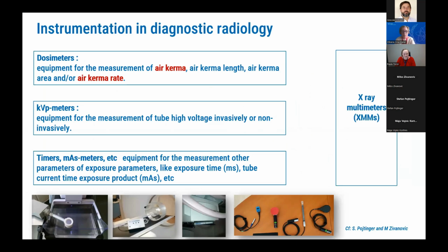For the measurable quantities in diagnostic radiology, we use different instruments that were extensively covered in the previous two talks. Both Miloš and Stefan mentioned different instruments aimed at those measurements, mainly in terms of air kerma, also for tube voltage assessment and measurement of other parameters like exposure time or tube current exposure time product, total filtration, half-value layer, and so forth. But in the last 20 years, all these parameters and quantities are somehow combined in one instrument that we call X-ray multimeter.